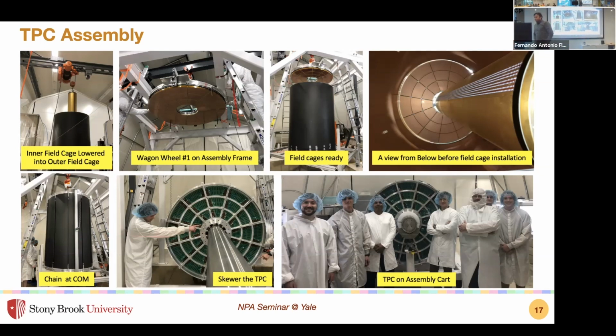This is also a very new thing - the seal is not an O-ring, it's spring energized, so it's a different kind of seal. It's kind of a rubber plastic thing, and it has a spring which is non-magnetic, because when the magnet quenches, it's not nice for your detector. You don't want the O-ring pulling out your entire hand, so you have to be careful there.